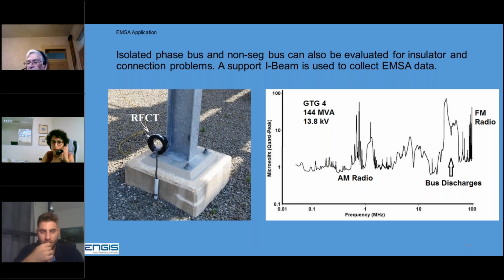Almost every bus will have some discharges all of the time. I think in 40 years of doing this, we've only found 3 or 4 buses that had no PD at all. Almost every bus has some minor PD like this has, and it's not a problem.